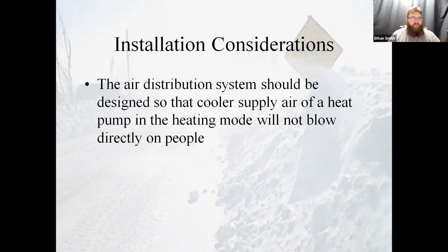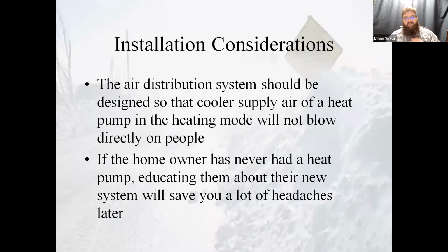Okay. Heat pumps have a lot lower discharge air temperature than a furnace typically, and so even though it is blowing air out that's heated, just the simple fact that that air is moving over an individual can be perceived as a cold draft. This is especially a problem with people who've never had heat pumps before and aren't familiar with how they work. So you may need to do some customer education in these situations. Okay. So doing that little bit of education for the customer will save you a lot of headaches on the back end. Letting them know what a defrost system looks like.